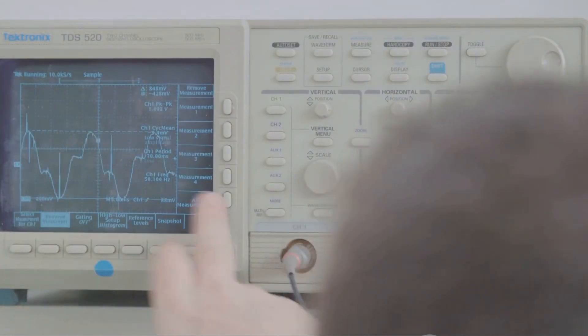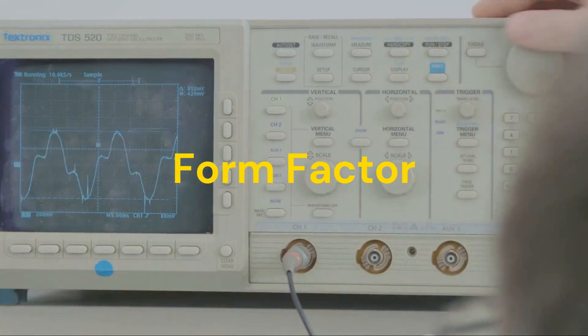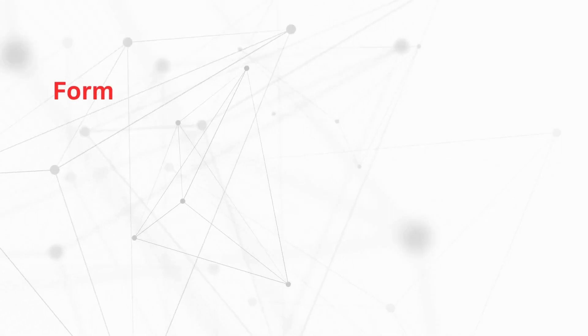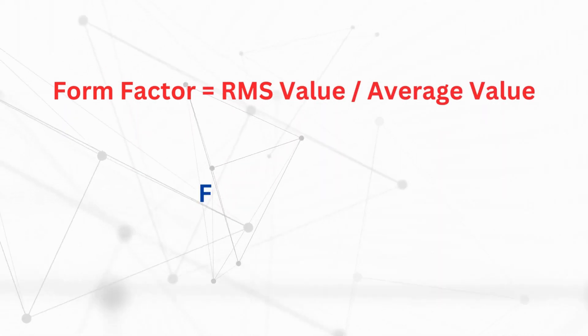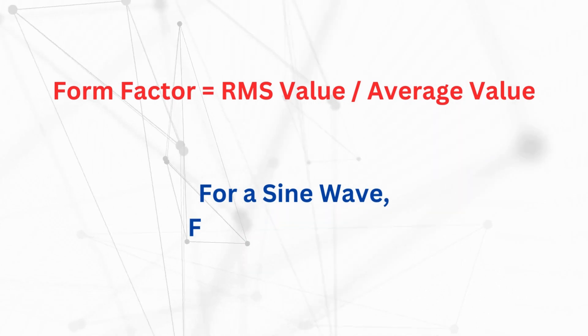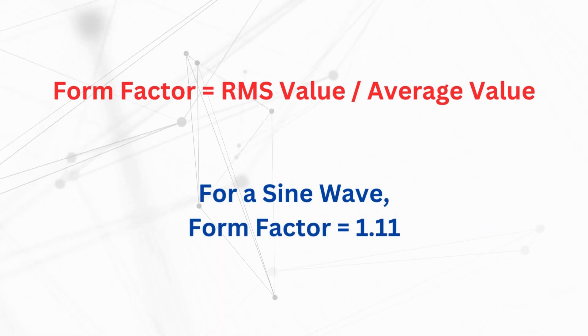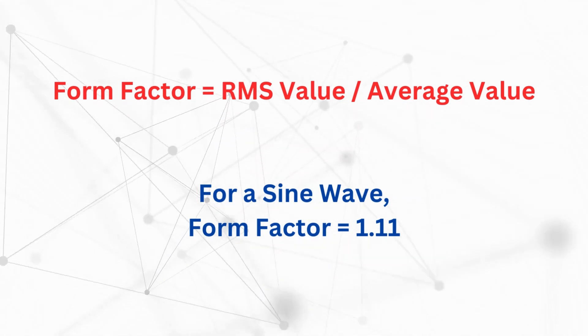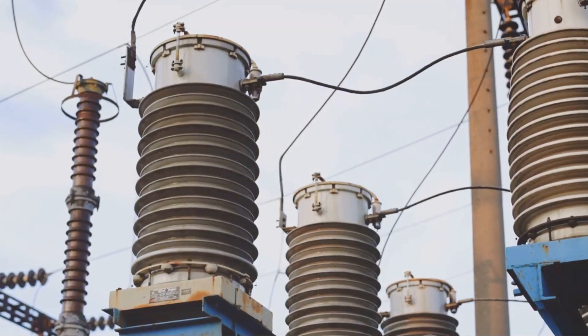One common theory attributes the 11 kV pattern to the form factor, a mathematical concept. The form factor is the ratio of the root mean square of a waveform to its absolute average value. For a sinusoidal wave, it is 1.11. It's a nifty mathematical concept indeed, but when it comes to voltage selection in power systems, it doesn't quite fit the bill.